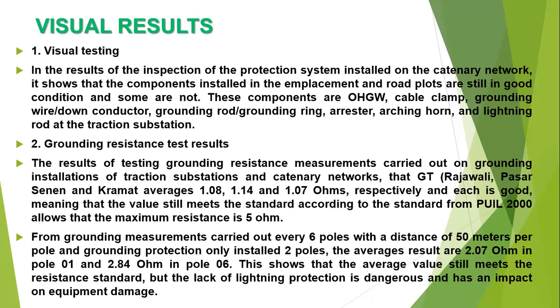Number 2, grounding resistance test result. The result of testing grounding resistance measurements carried out on grounding installations of the traction substation and catenary network, the GT, Rajawali, Pasar Senen, and Kramat, average 1.08, 1.14, and 1.07 ohms, respectively, and it is good, meaning that the value still meets the standard. According to the standard from PUIL 2000, the maximum resistance allowed is 5 ohm.